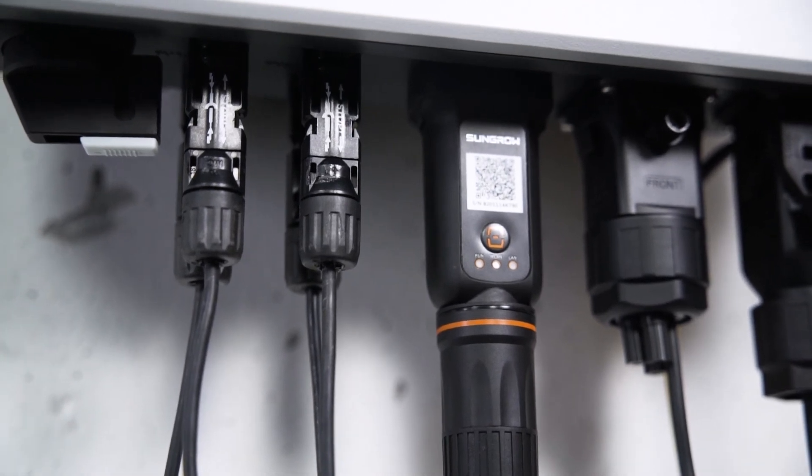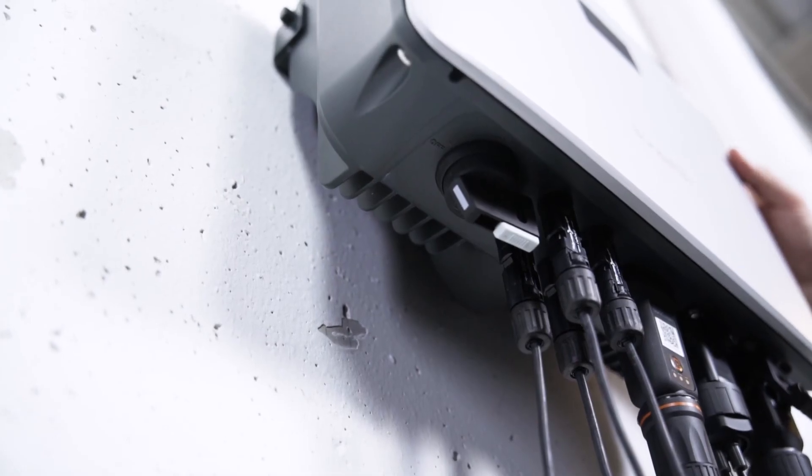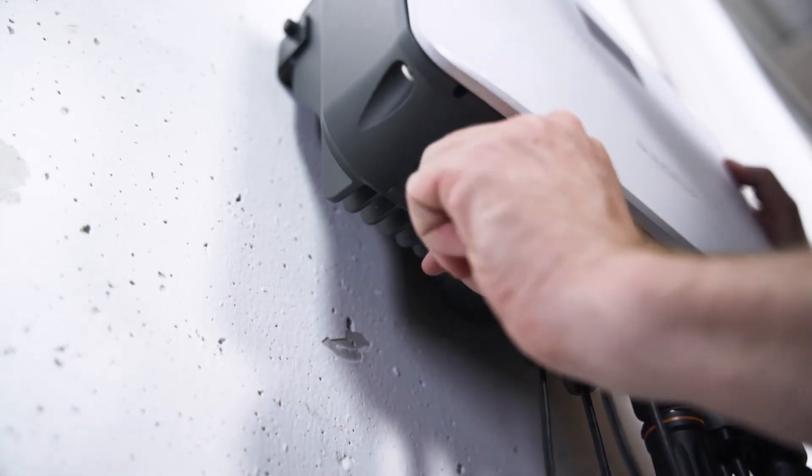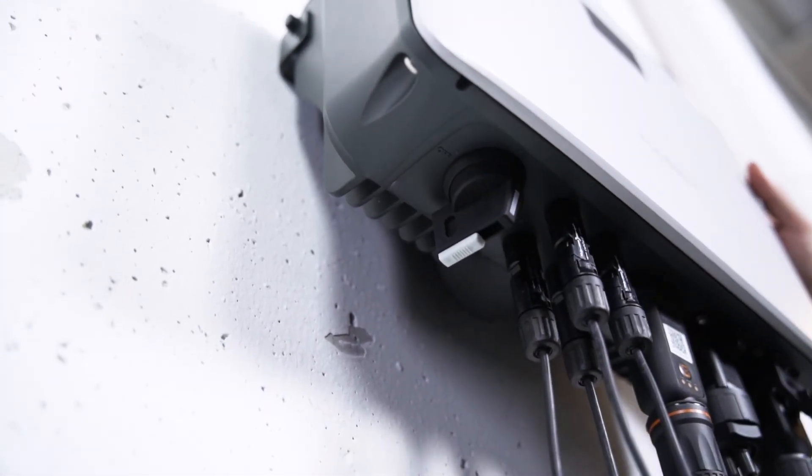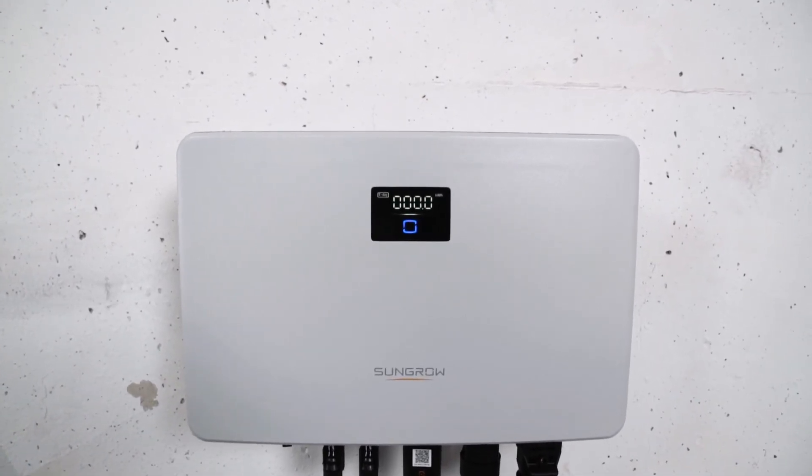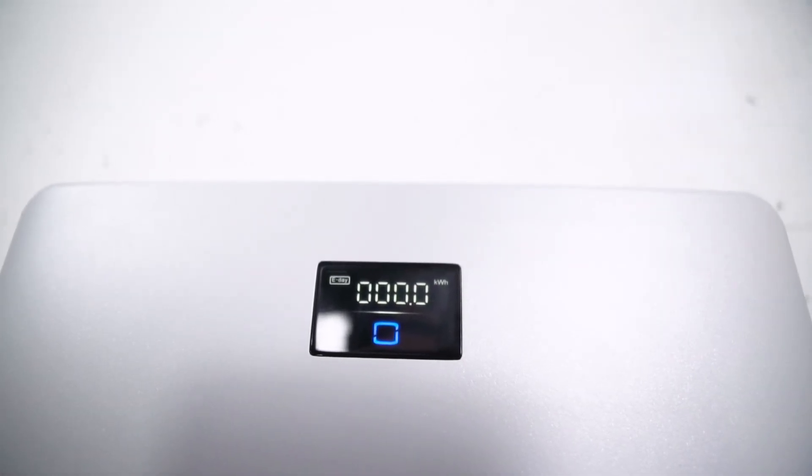Now it's time for commissioning. First, you have to set the DC switch of the inverter to the ON position to connect the inverter to the PV generator. Next, you have to switch ON the AC circuit breaker. A look at the LED light tells you if everything works properly. If the light shines continuously blue, the inverter is ready for use.